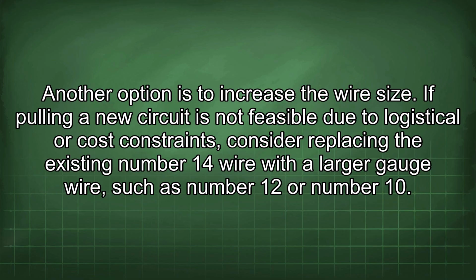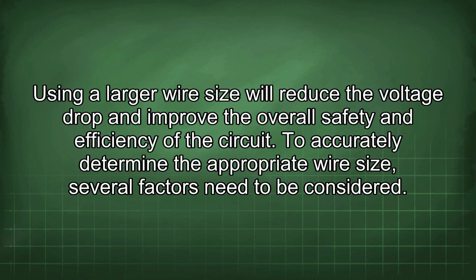Another option is to increase the wire size. If pulling a new circuit is not feasible due to logistical or cost constraints, consider replacing the existing number 14 wire with a larger gauge wire, such as number 12 or number 10. Using a larger wire size will reduce the voltage drop and improve the overall safety and efficiency of the circuit.